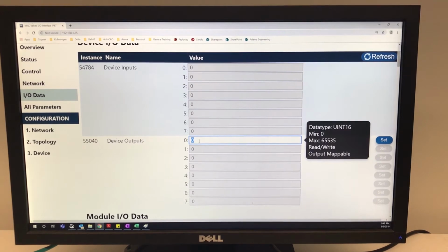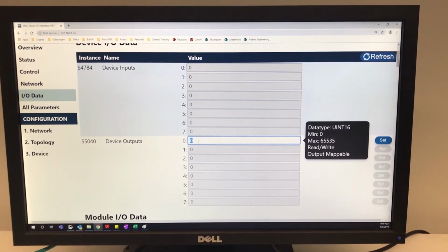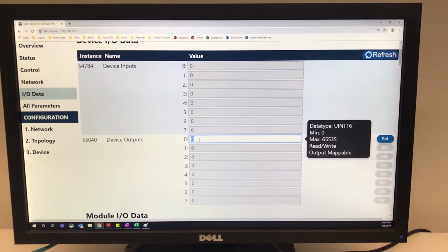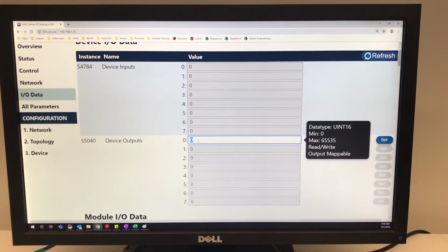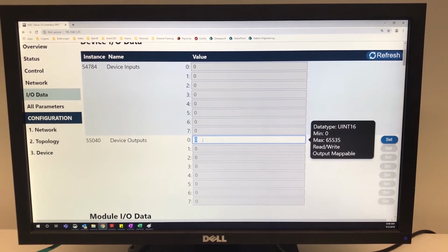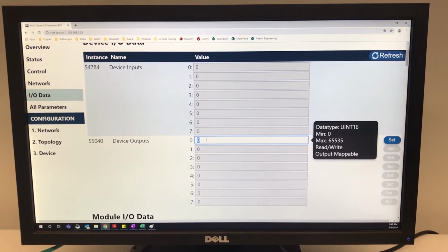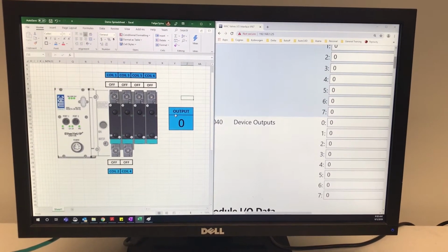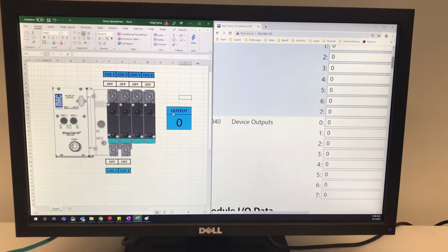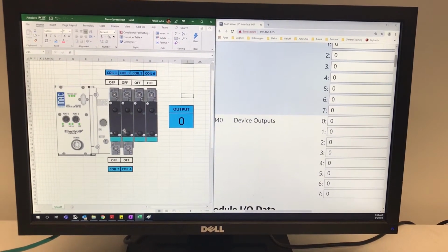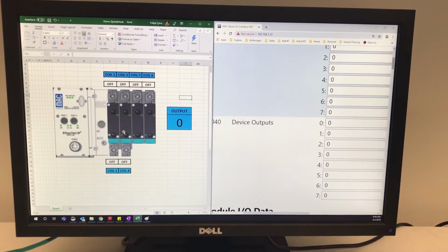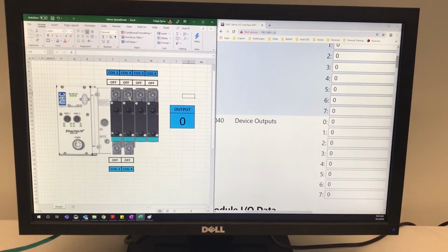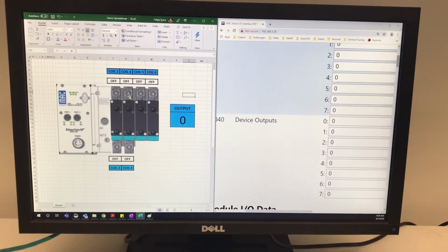This field takes the decimal value corresponding to the binary string that the PLC would be sending to the MAC manifold. In other words, we're simply mimicking the PLC communicating with the manifold through this field. Since I know that many of you might not be familiar with binary, I made here on the left this binary converter that is designed to simplify the operation of the manifold through the web interface.